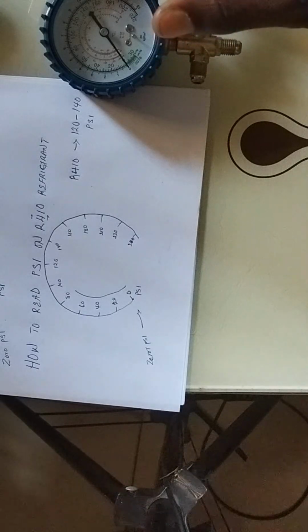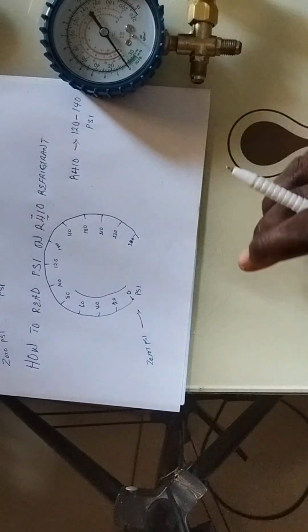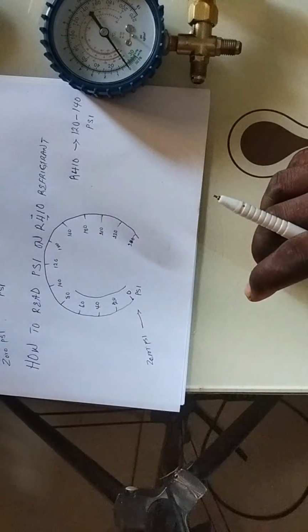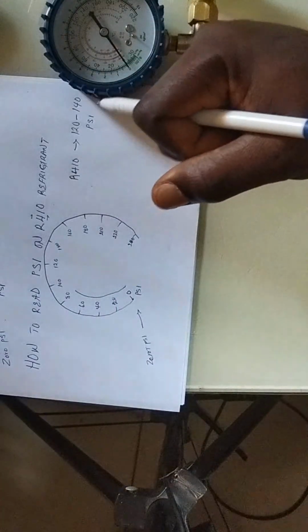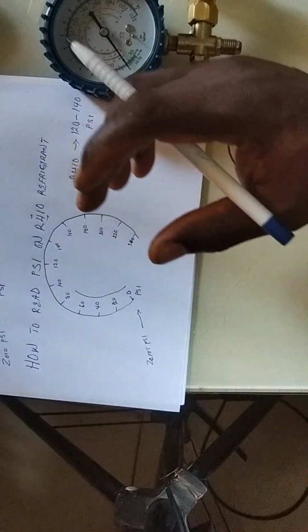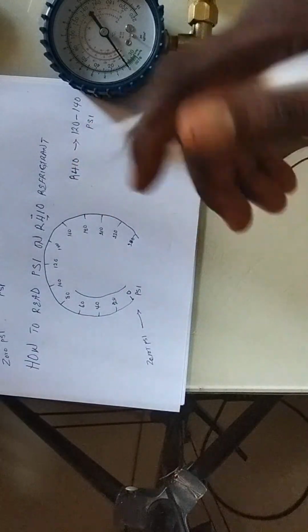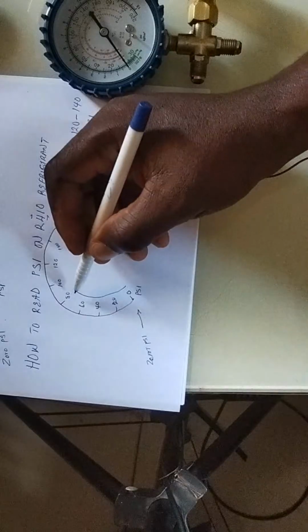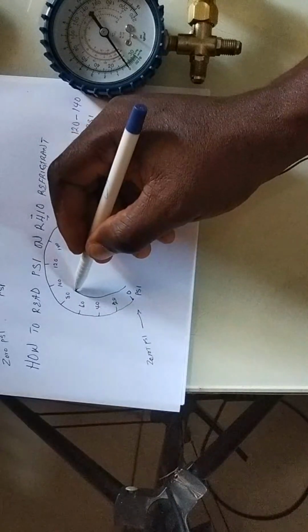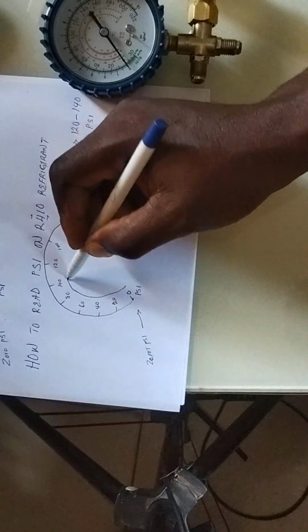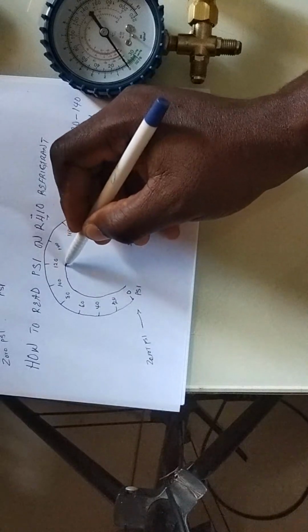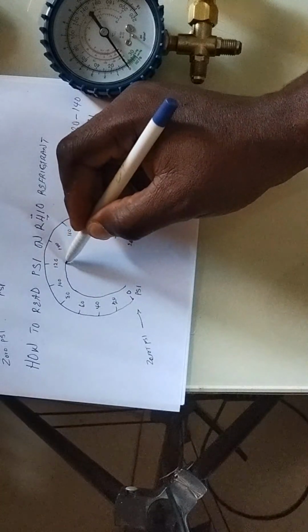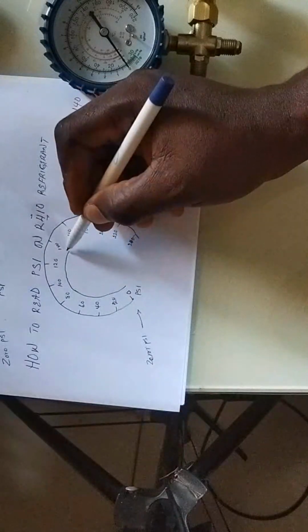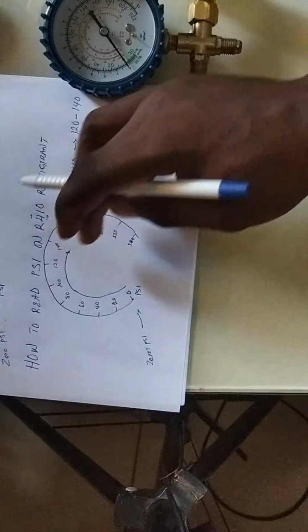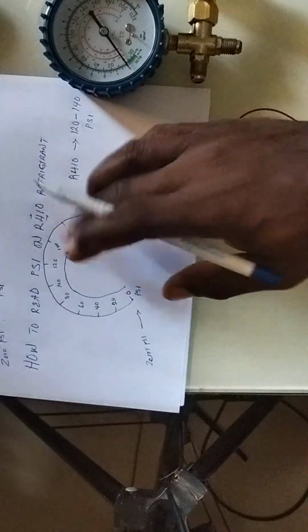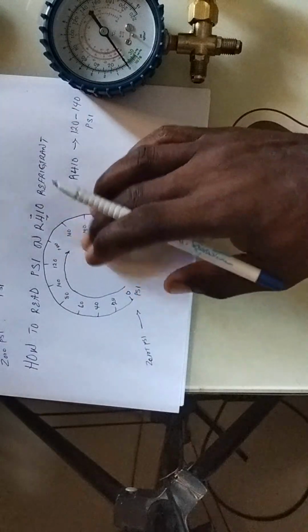I don't know if you get my point. The discharge line of that air condition will start freezing, will start forming icing. With that point, that's where you know that, okay, that's where your expansion starts. But you don't stop charging up the refrigerant, you still keep going. You increase it up to 100, you increase it up to 120. If you can still increase it up to 140, that 140 psi, you set it up, that is where you are good to go.